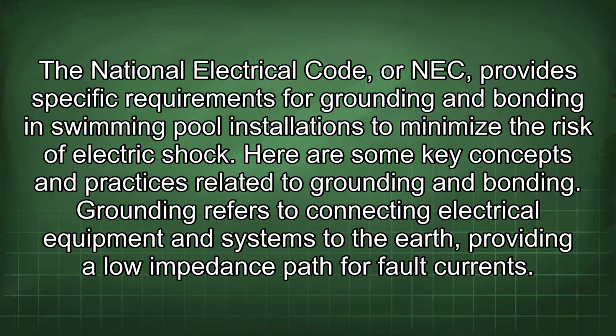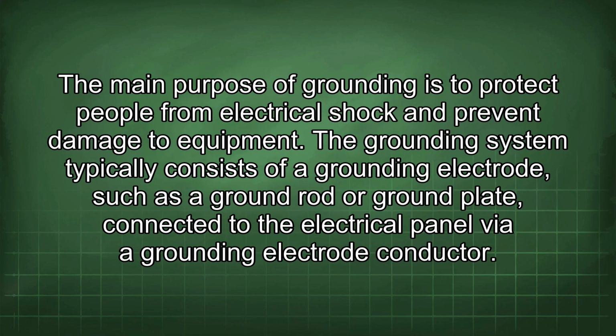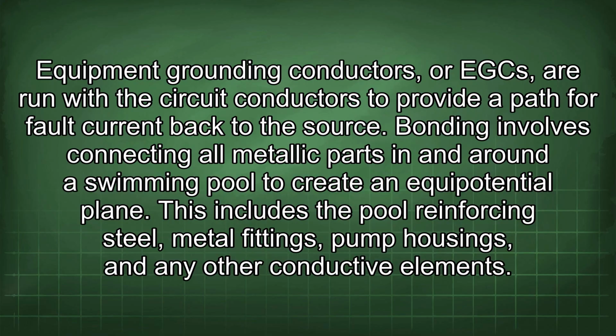Grounding refers to connecting electrical equipment and systems to the earth, providing a low impedance path for fault currents. The main purpose of grounding is to protect people from electrical shock and prevent damage to equipment. The grounding system typically consists of a grounding electrode, such as a ground rod or ground plate, connected to the electrical panel via a grounding electrode conductor. Equipment grounding conductors, or EGCs, are run with the circuit conductors to provide a path for fault current back to the source.